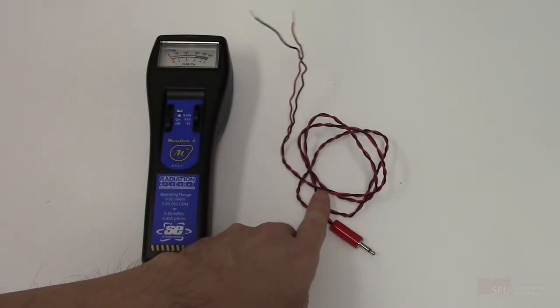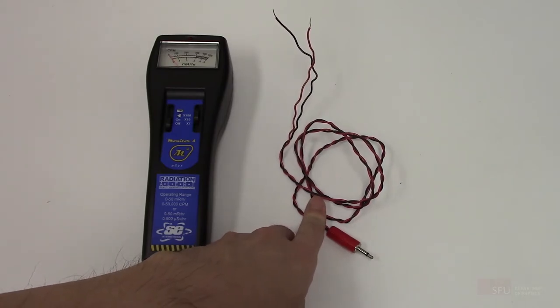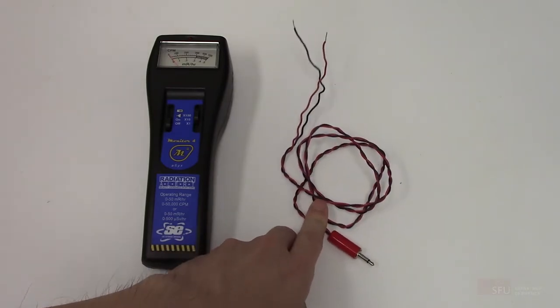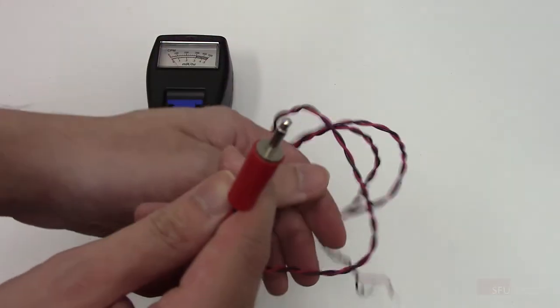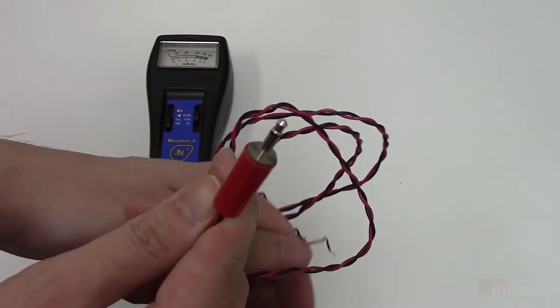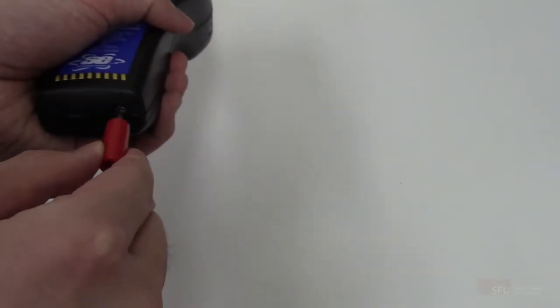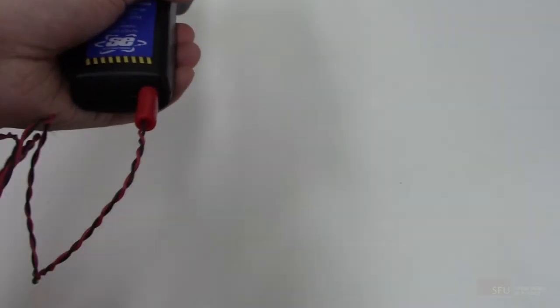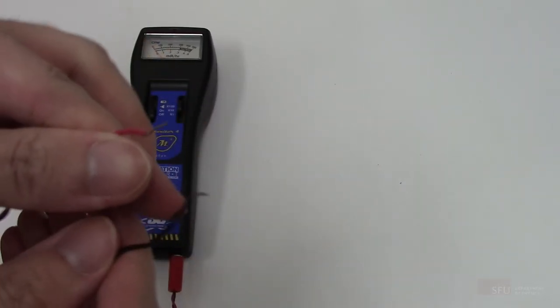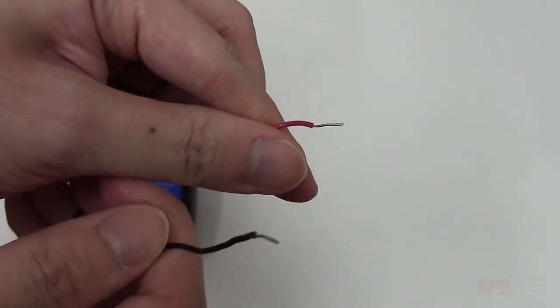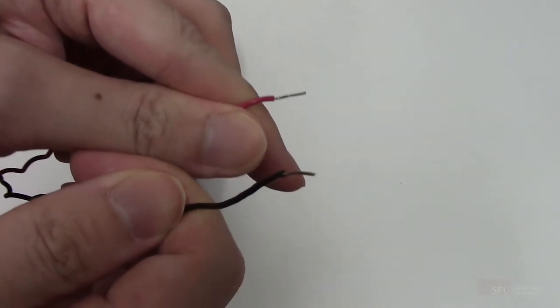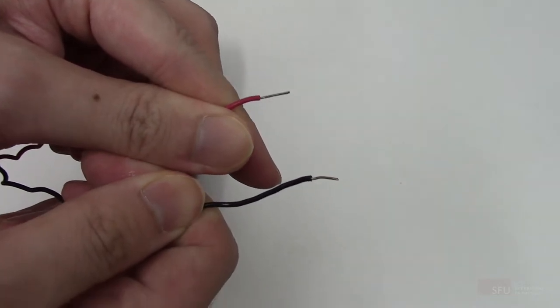This is the interface cable between the Geiger counter and the DAC. This end goes into the bottom of the Geiger counter and these wires go into the DAC. The red wire goes into PFI-8. The black wire goes into DGND.